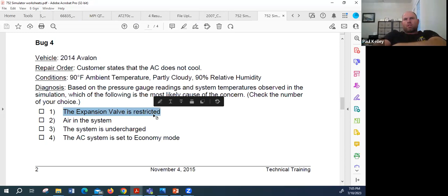And if it draws into a vacuum, there's very little refrigerant that's actually going to flow through. So we might be getting evaporation, but it's a very small quantity occurring. So what's going to happen to all that heat we were planning on absorbing through evaporation? We don't have a substantial quantity of evaporation. So are we going to get the cooling? No, I agree. And so I'm very happy with my answer, jumping over to the TXV is restricted, because I can measure that, and that would be my choice.